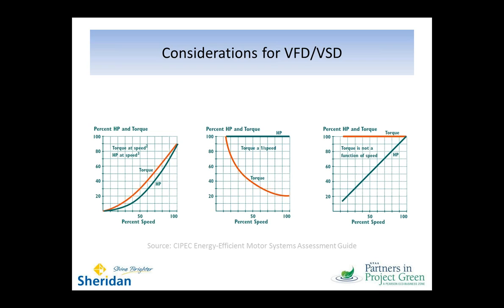But it's not all rosy. Not all end uses are created equal. The application on the left is one where we see variable torque and horsepower. So I'm able to change speed, and as I'm changing speed, I'm seeing the torque and horsepower respond. That's the kind of load that's following the affinity laws. So loads like this are centrifugal fans, pumps, blowers. And if I'm running a variable speed drive between 100% speed and 50% speed, I could be seeing really big savings out of that bunch.